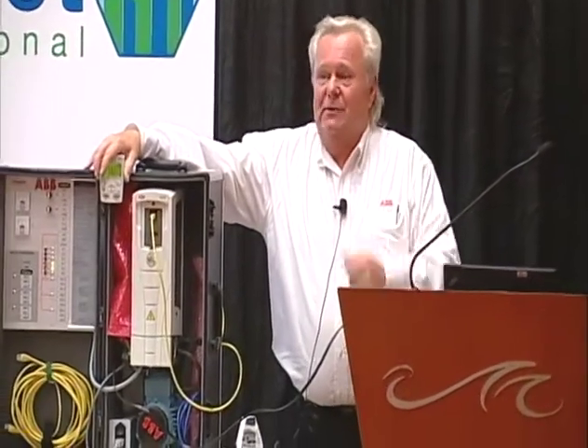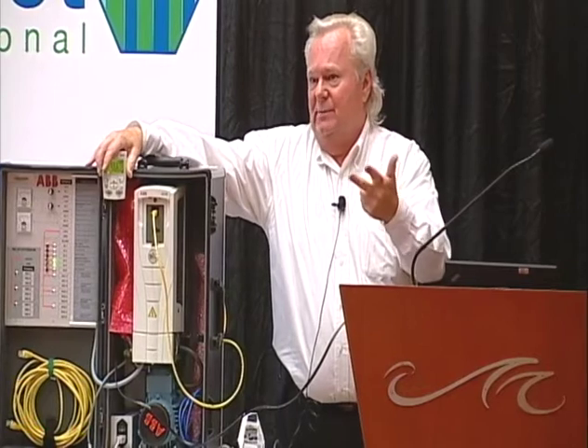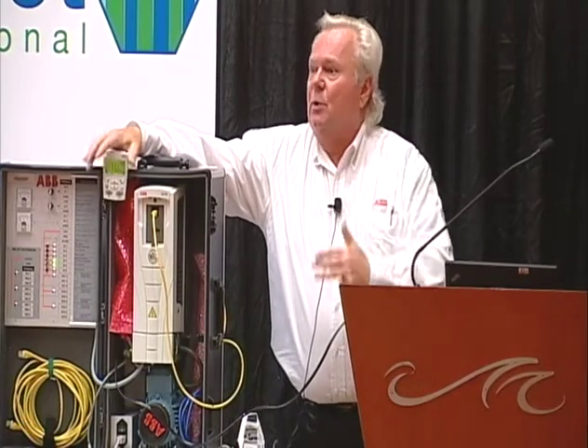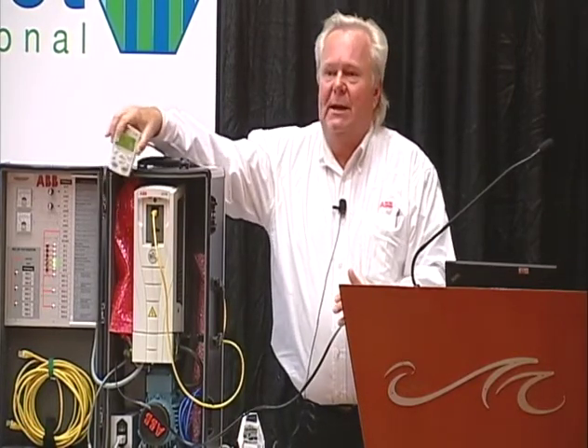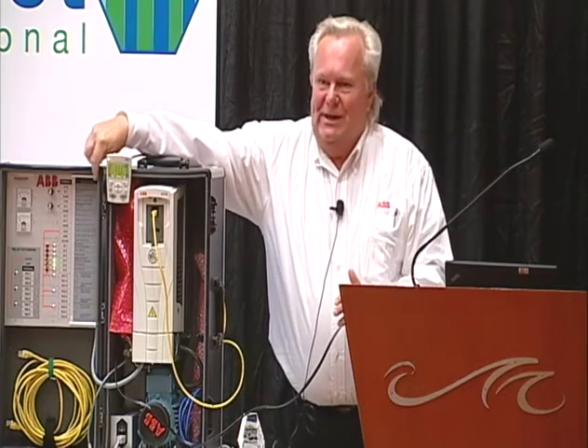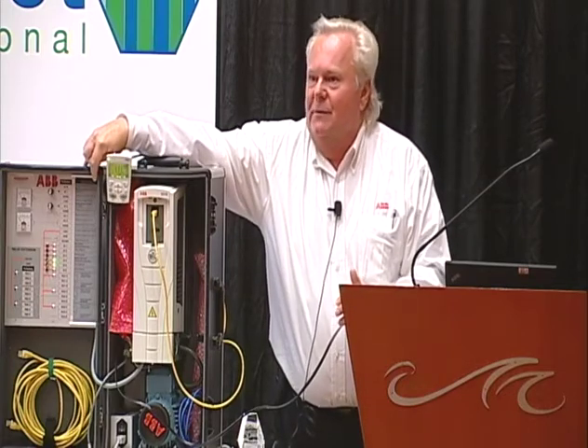Well, ABB chooses to have quantities of scale. In electronics manufacturing, the name of the game is volume. If you build 1 million printed circuit boards, it's cheaper than building 500,000. So rather than have one design for the industrial side and another design for HVAC, we have the same hardware. Now there's different software on an ACH 550 drive. You've got BACnet, Johnson N2, Siemens FLN, and Modbus protocols. You've got a special keypad, hand-off-auto. But the hardware inside is the same. It's just got different software and a different keypad.